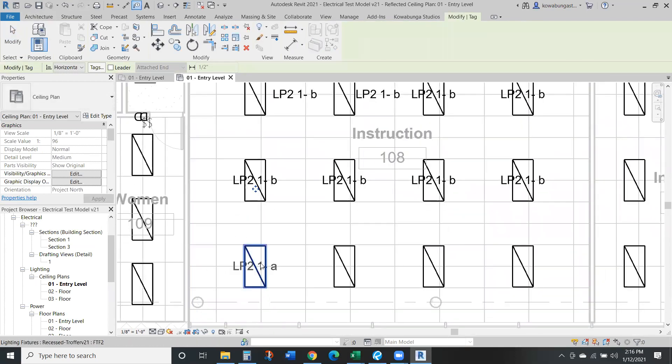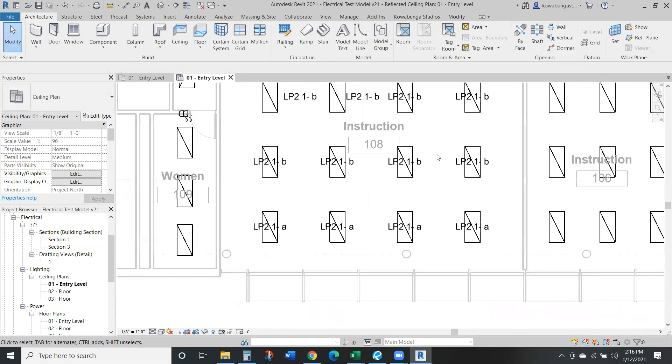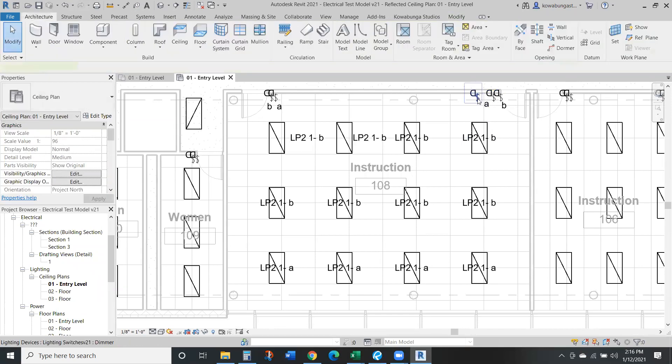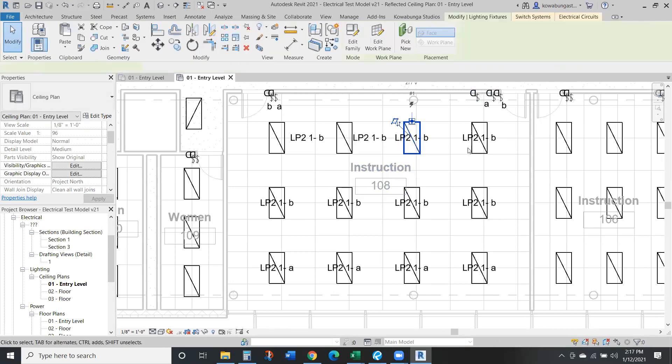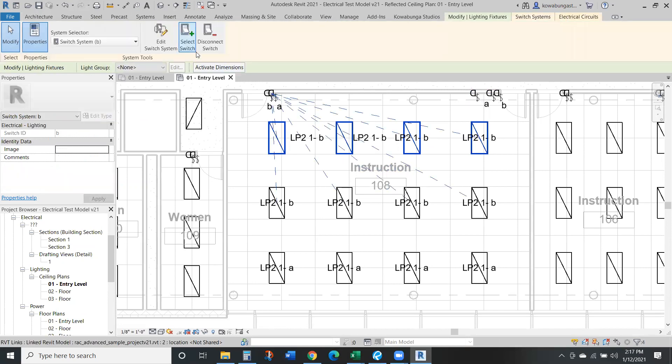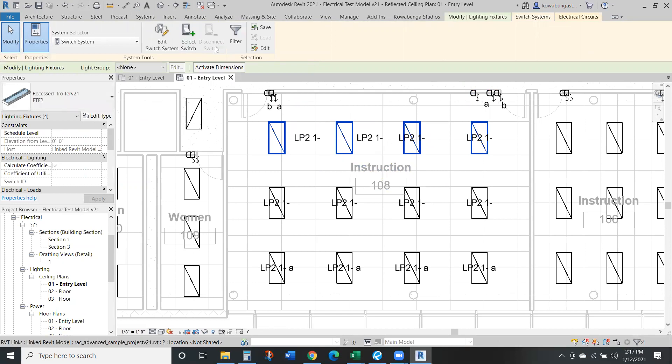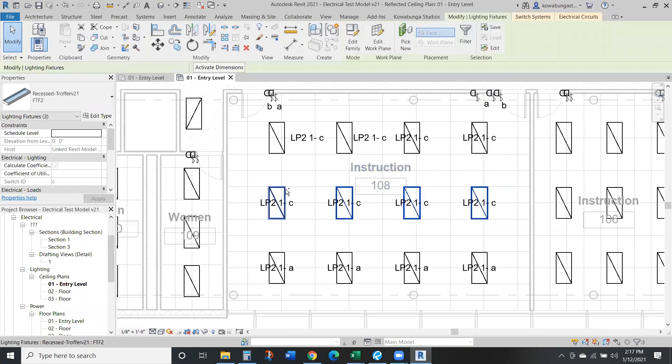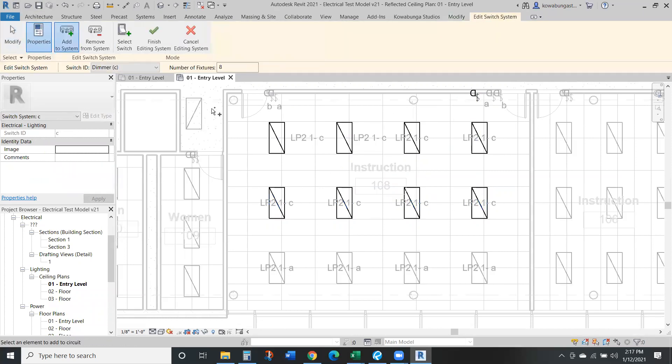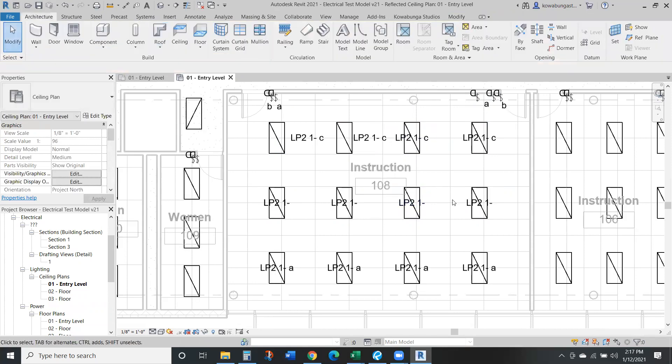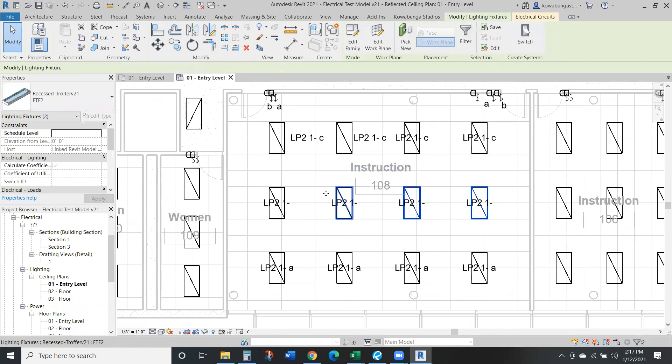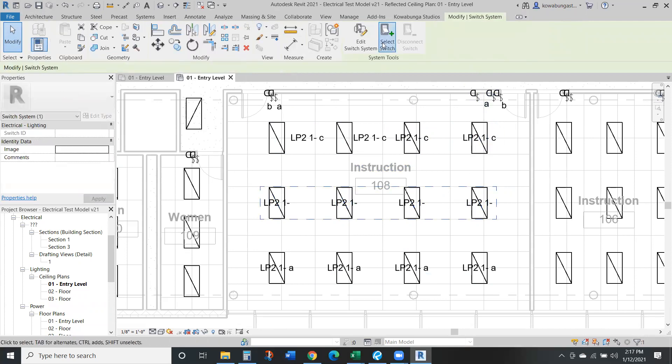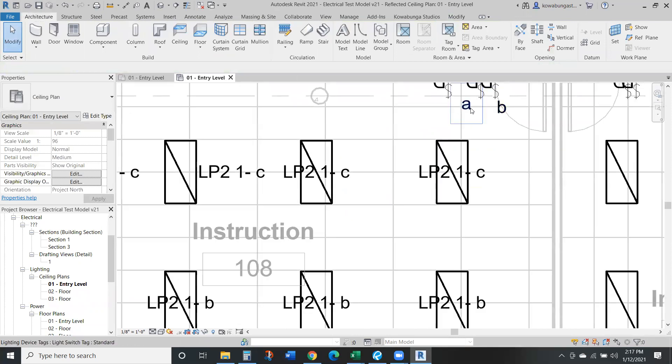One of the things we're also going to show here is we got your A and B, but let's say you added another switch in here. We'll call this one C. With your switch leg, let's say you wanted these four fixtures onto a different switch. First you need to disconnect them from the switch leg. Select the switch you want, so it's going to be C. You can see that they move switch systems. We're going to edit the switch system first. Remove these from this switch system. In these four fixtures, we'll change the switch that they're connected to. So switch, and then select switch, and A, B, and C. Then create similar C switch here.